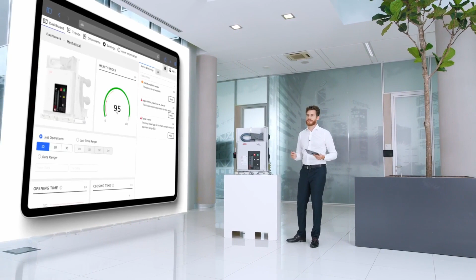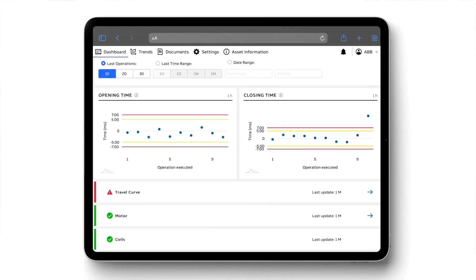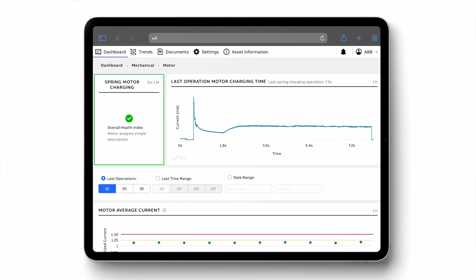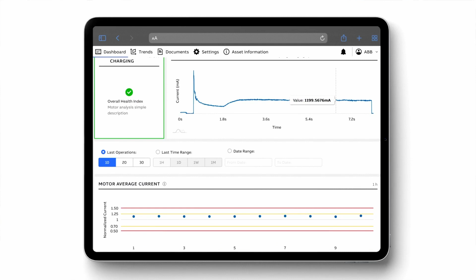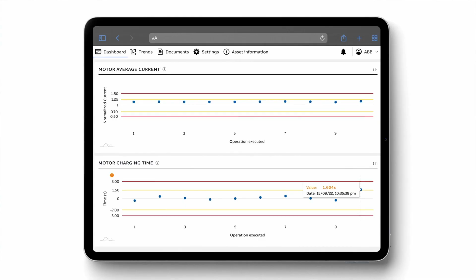The accessories are also monitored. For example, the charging motor device can be influenced by operating conditions over the years and display signs of wear. Therefore, we monitor the current absorption profile and advise on a simple accessory replacement before it's too late and worse damage is done to the equipment.